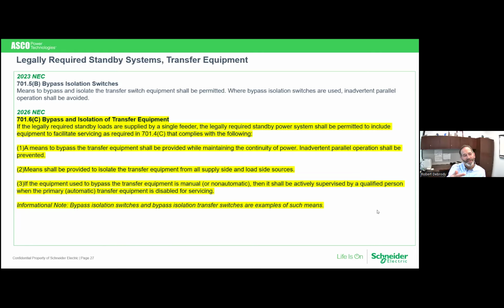But sadly, by removing that paragraph that was in 2023, they're in essence saying, which they didn't mean to do, or implying, if you're going to read this in the literal sense, that the only time you can use a bypass isolation switch now is when you have your standby load supplied by a single feeder, which is not what they intended.